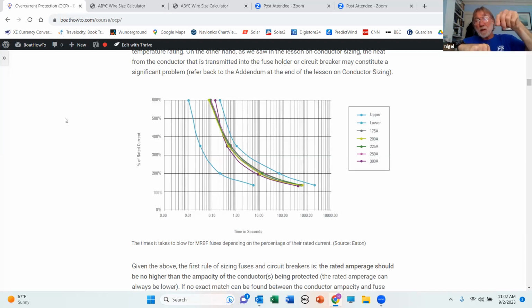Well, we didn't notice that one of the washers had dropped down, and now instead of being on top of the fuse, it's underneath it. So it's now between the conductor terminal and the fuse. That washer is going to act like a little heater, quite a big heater. If we start running high amps through that conductor on a continuous basis, which we will be doing if we've got a high output alternator charging a discharged lithium ion battery bank or even a discharged large lead acid bank, that single stainless steel washer can get hot enough to start a fire. What it may also do is generate enough heat to melt the fuse, even though we don't have an overcurrent situation. And when the fuse melts, it'll destroy our alternator.